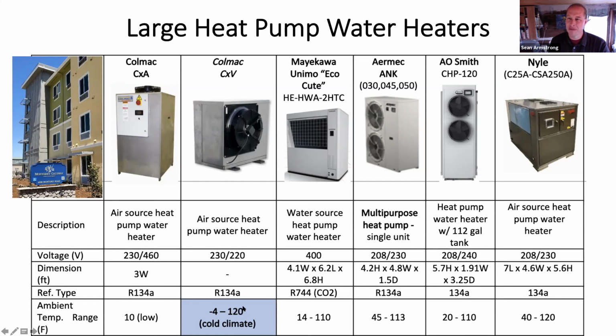You want to be more like 130 to 140 Fahrenheit, so you have two choices: either an electric resistance element for the last bit, or feed this 120 degree water into a water-to-water heat pump that concentrates the heat further, taking it from 120 up to 190. That covers the hot water for a radiator system, which runs at 180, 170, even 160 Fahrenheit. Depending on which type of heat pump you use, this range of products can cover from -30 Fahrenheit up to 180 Fahrenheit if you combine an air source and a water source. With just an air source, you're down around -30.